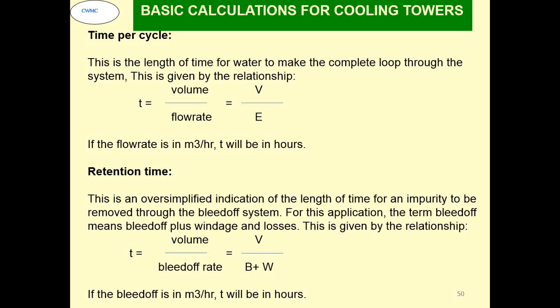Retention time is, in oversimplified indication, the length of time for an impurity to be removed through the bleed off system. For this application, the term bleed off means bleed off plus windage and other leakage losses. This is given by the relationship T equals V by B plus W. The bleed off is again in meter cube per hour and T will be in hours.